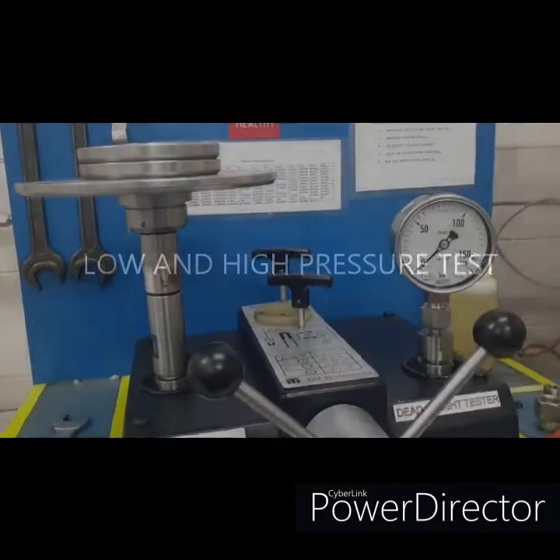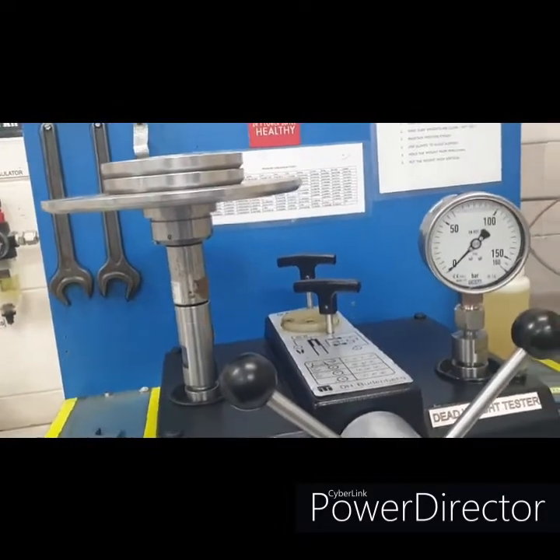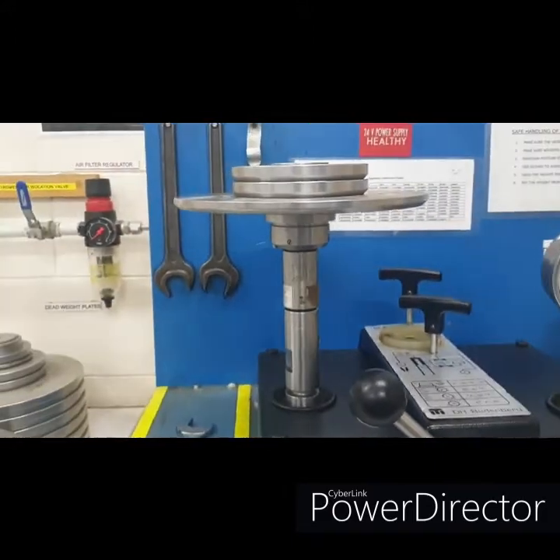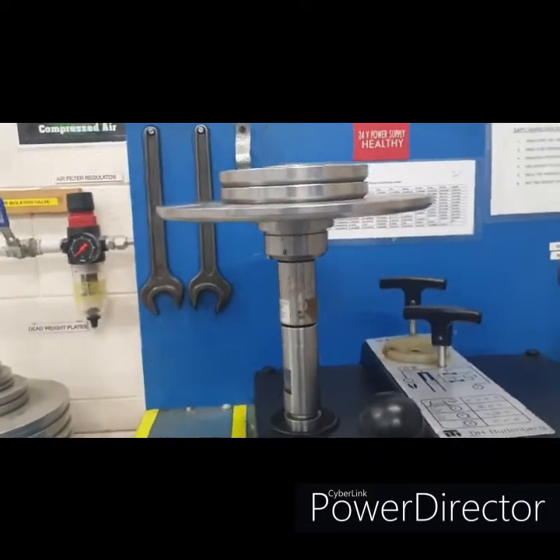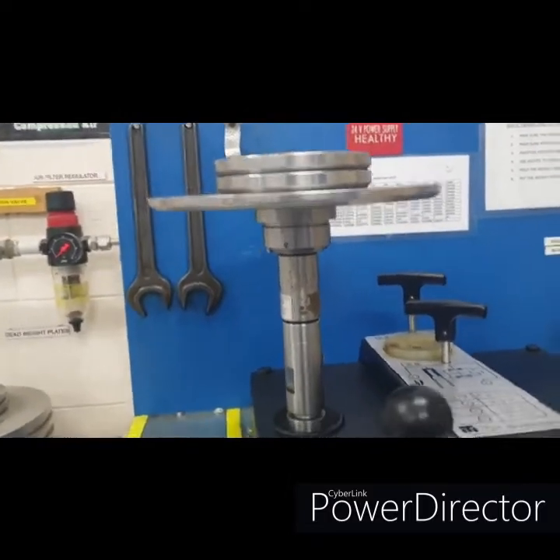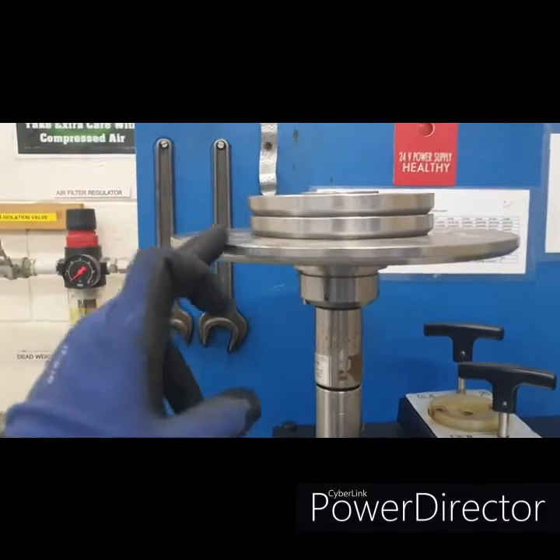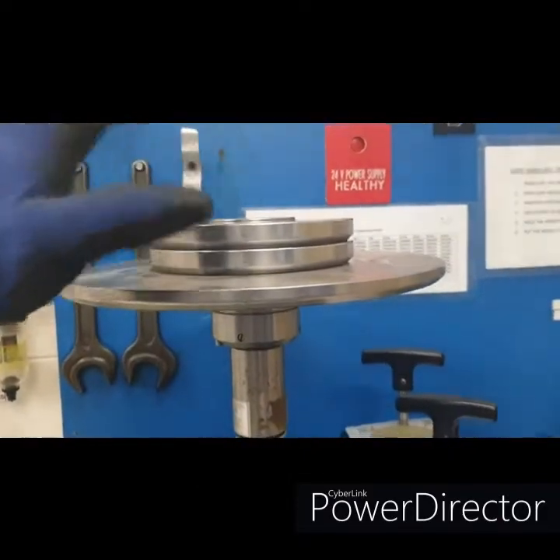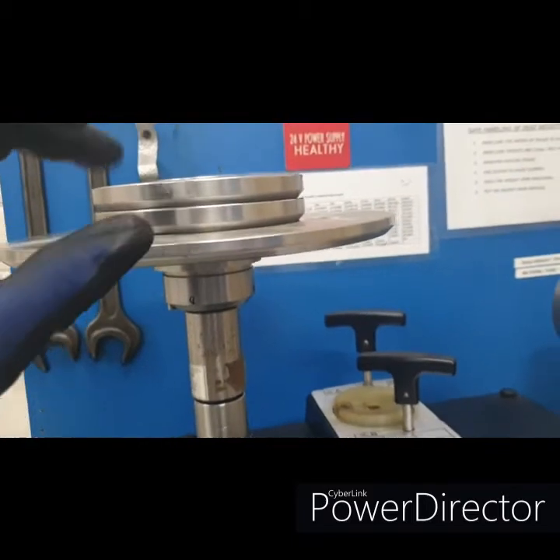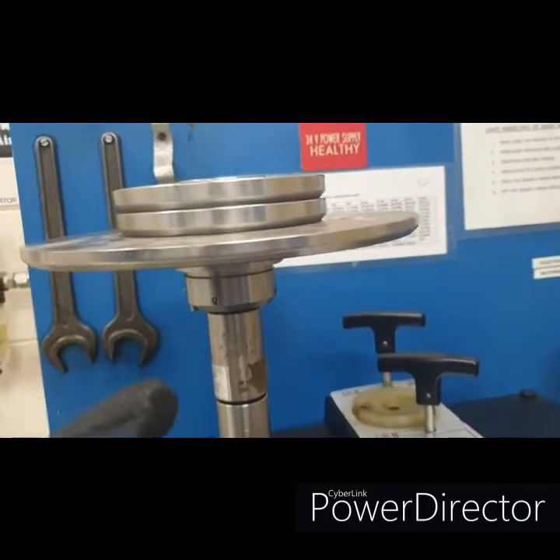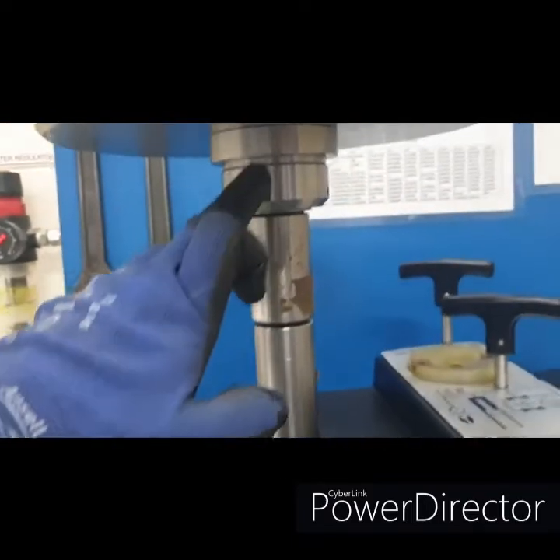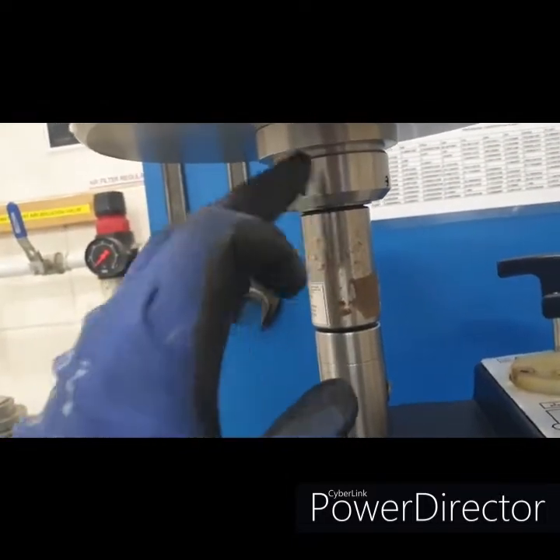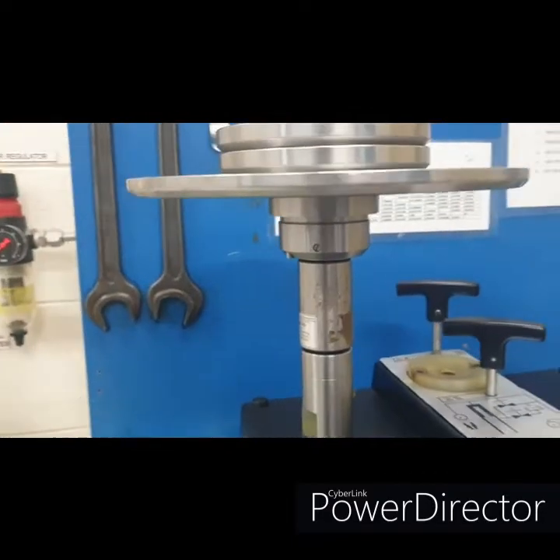All right, so we're going to test the low pressure and the higher pressure. I am putting multiple plates with a total weight of 10. So basically this big plate is a 5 bar and the two plates here are 2 bar each. So 5 plus 4, it's 9 plus the default weight of the makeup weight plus the carrier weight 1. So it's a total of 10.